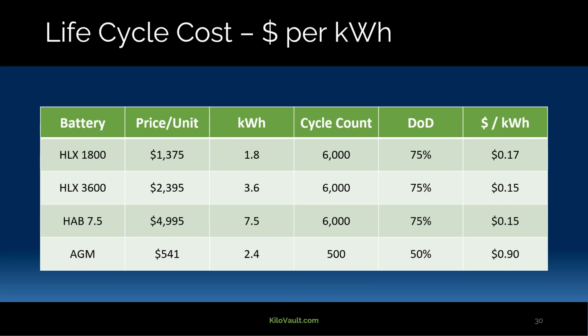So this example of an AGM battery got only about 500 cycles at 50% depth of discharge. The manufacturer actually recommended going a little bit lesser than 50% depth of discharge, but since 50% is typically what's used, that's what we use for comparison's sake. And you'll see that the cost per kilowatt hour is tremendously lower, like I said, for the lithium options. And, like Jake was saying, the tricky part with a lot of these lithium iron phosphate systems is that upfront cost. But when you're able to explain to the end user that you're going to need to replace the AGM battery 12 times over the course of its lifespan as compared to what the lithium would be, all of a sudden that upfront cost looks a little bit more palatable.